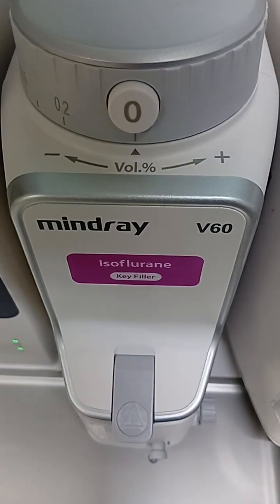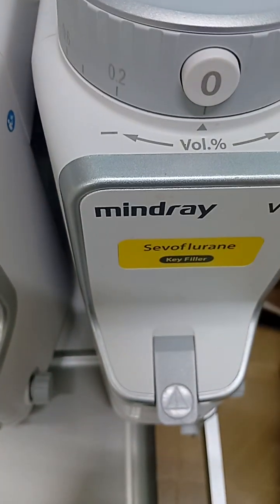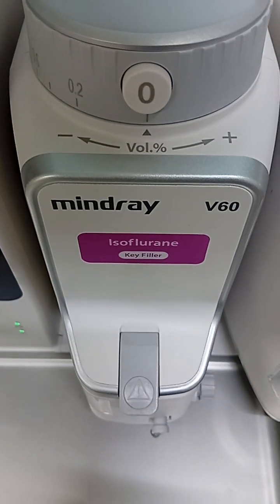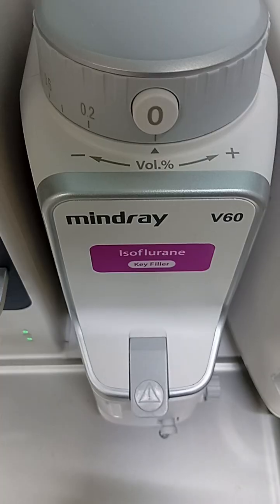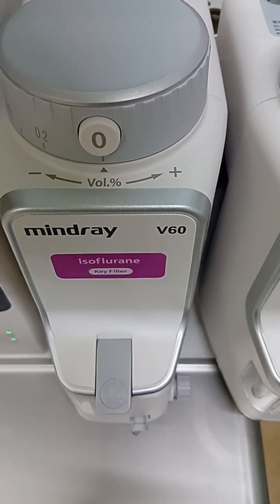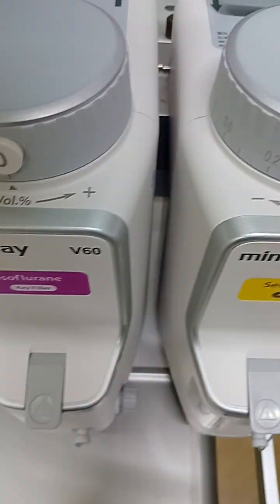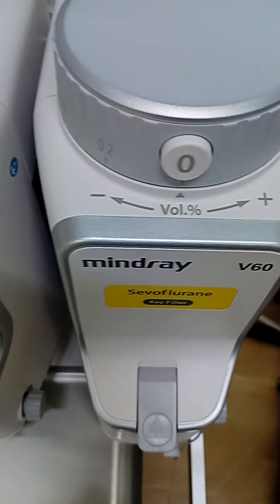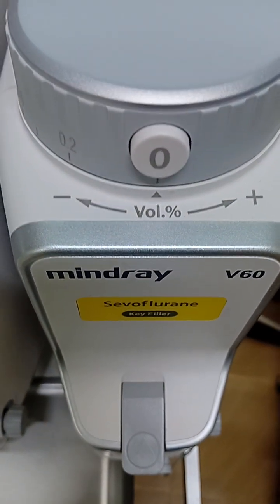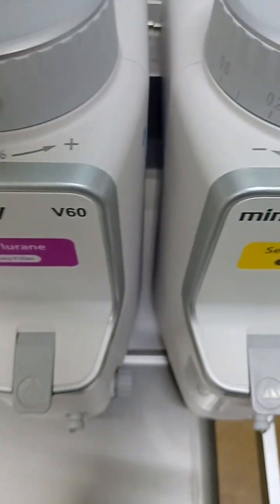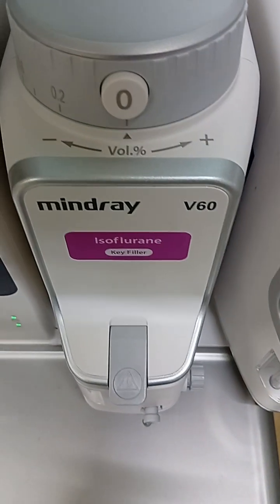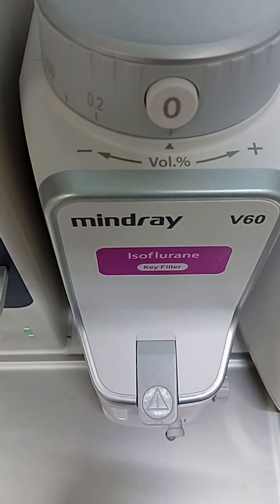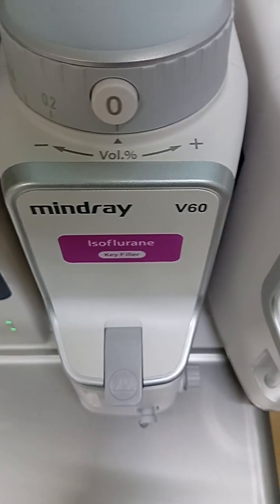The reason why they are color coded is to make sure that you do not confuse them. This is some of the safety features again that the manufacturers continue to add to make sure that you do not add the wrong agent to the wrong vaporizer.